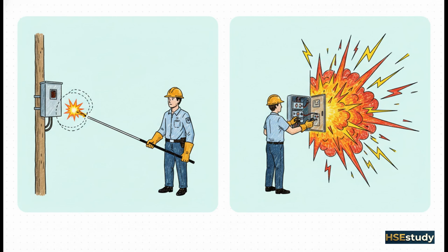And this slide just drives that point home. It's what we call the proximity multiplier effect. The worker on the left, dealing with 13.8 kV, is using a hot stick. He's keeping himself 4, maybe 5 feet away from the danger. But look at the electrician on the right, troubleshooting that 480-volt panel. He's right up in it, maybe 18 inches away, just arm's length. That proximity alone multiplies his energy exposure through the roof. And we haven't even gotten to the second variable yet.